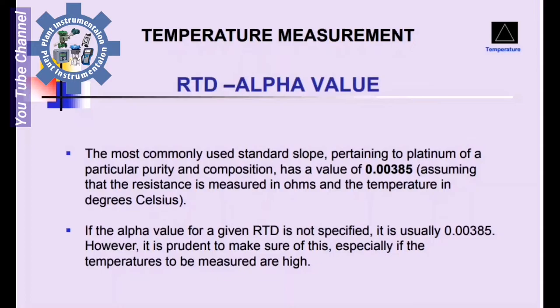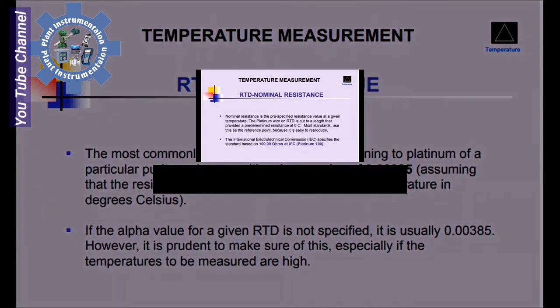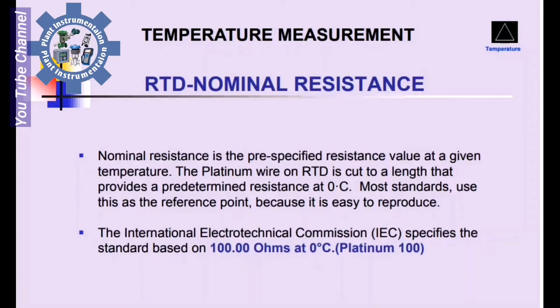If the alpha value for a given RTD is not specified, it is usually 0.00385. However, it is important to make sure of this, especially if the temperatures to be measured are high. Nominal resistance is the pre-specified resistance value at a given temperature. The Platinum wire on an RTD is cut to a length that provides a predetermined resistance at 0°C.